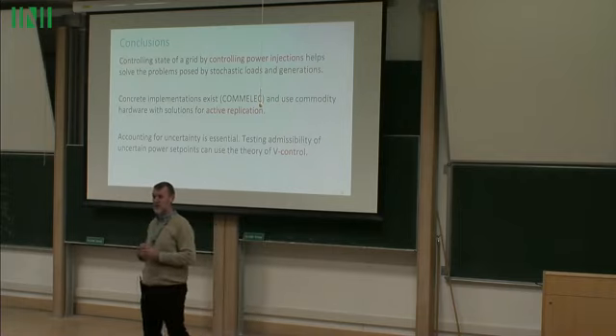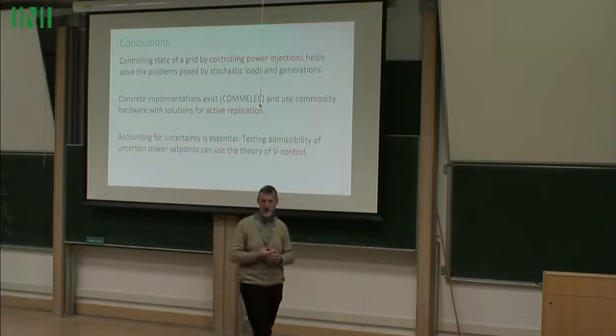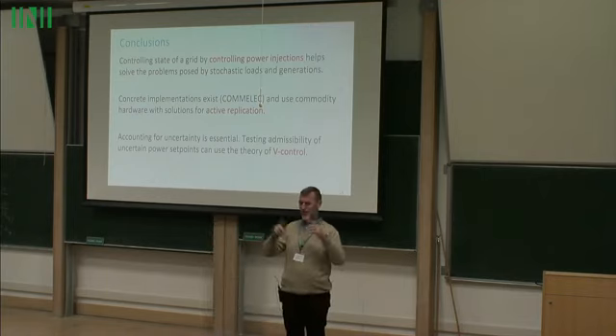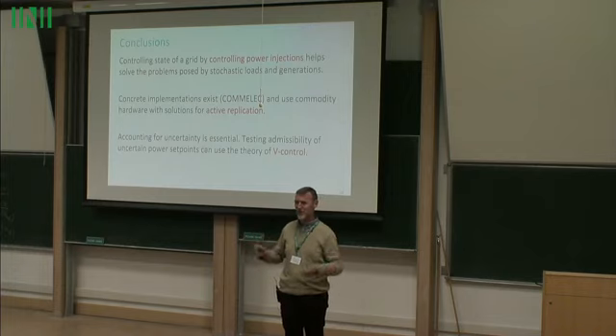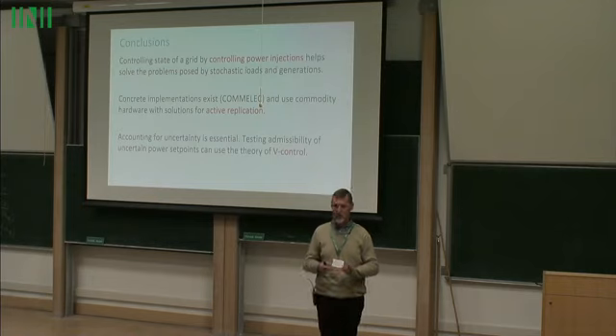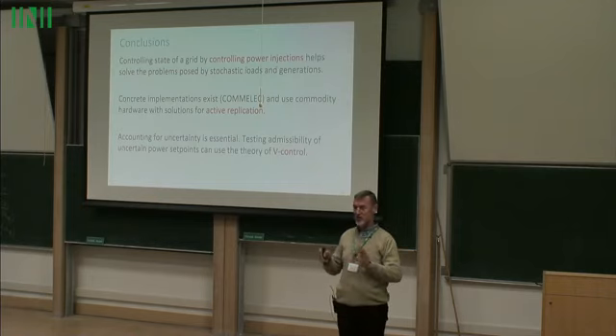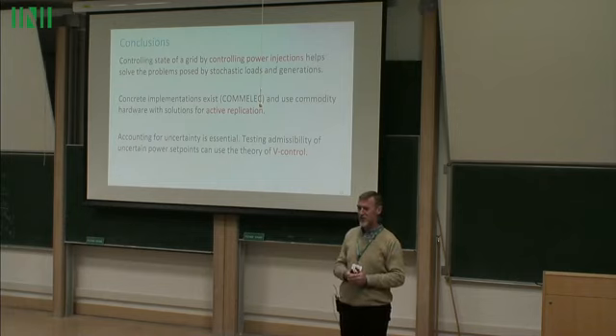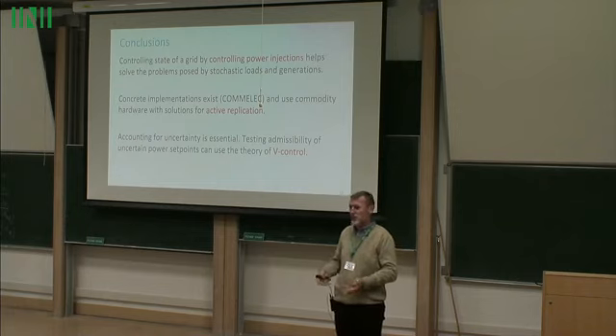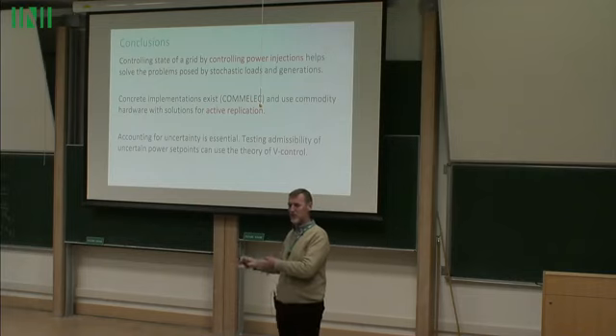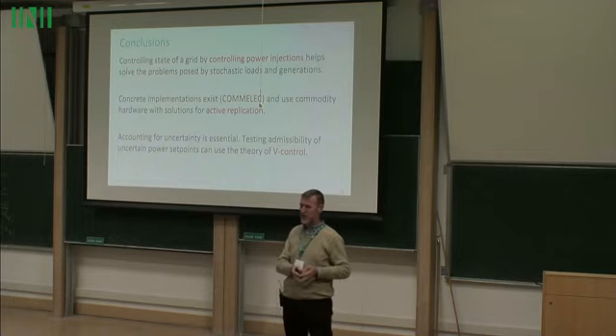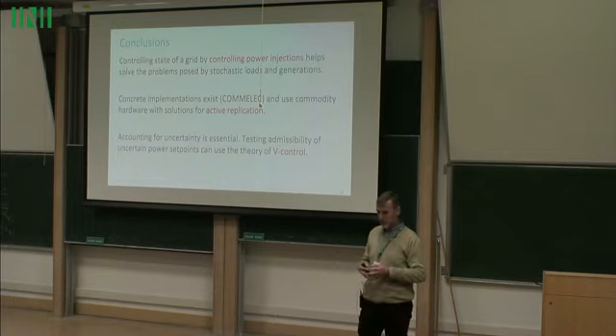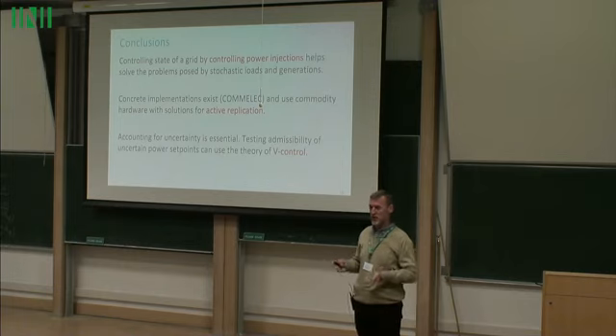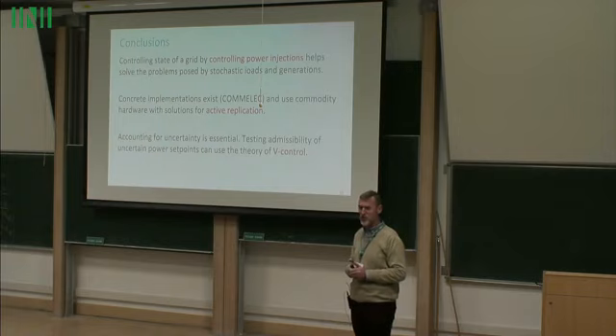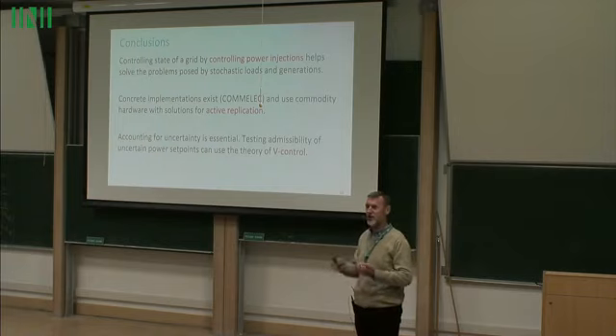We are deploying this in the grid of a big Asian city, where they constantly change the topology of the grid very frequently. Although it's a distribution network, it remains single slack, but changes often. The timescale where we do it is only a software problem. A startup is commercializing this software, and one thing they've done is make dynamic changes - we need to change the Y matrix, since all control is based on the Y matrix specification.